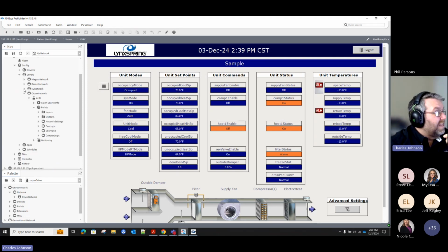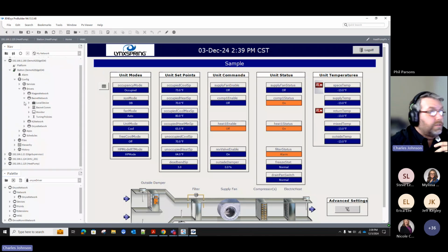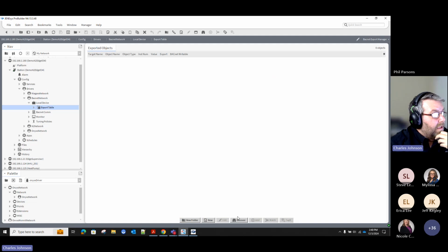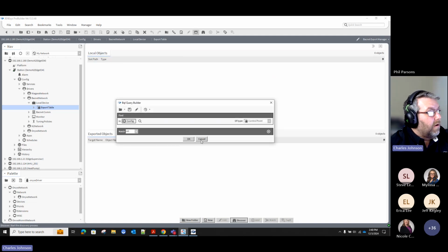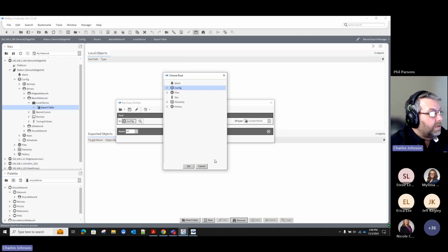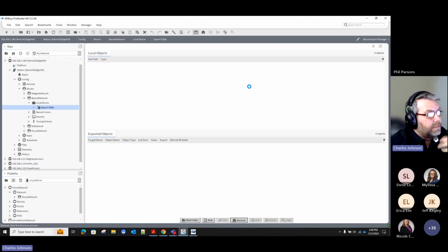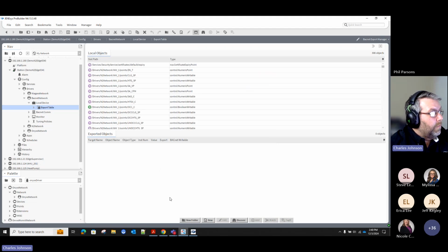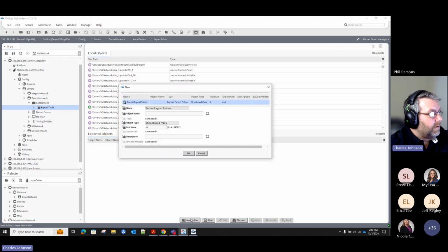But let's say that this here needed to talk to, let's say you didn't have a Niagara front end. Let's say you had an SC front end from, like, Trane with the Trane Tracer SC or the SC Plus. Well, if you add a BACnet network, and as long as you set up your network appropriately, we can go to the export table and discover all of our devices or all of our objects underneath here.